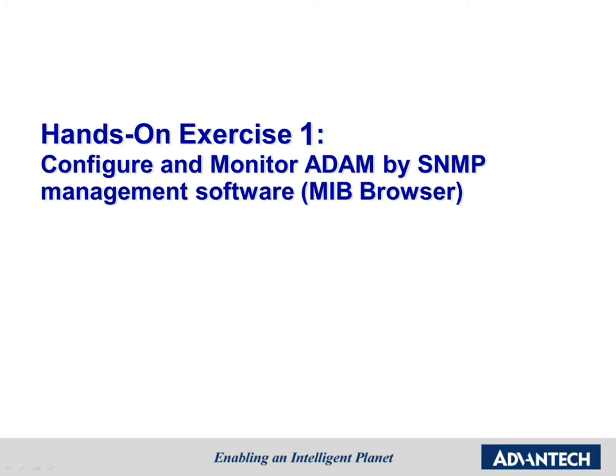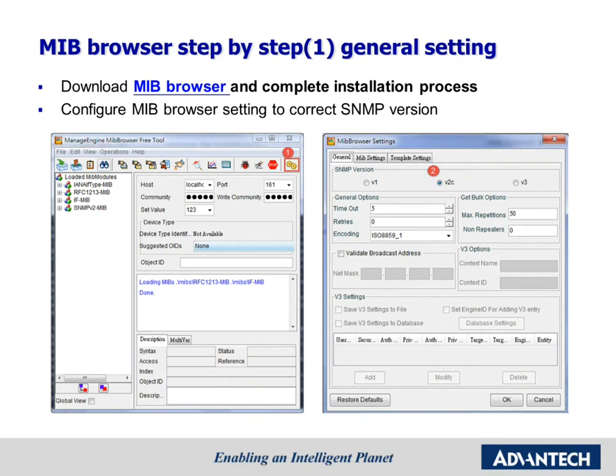Let's go to the first hands-on: configure and monitor ADAM by SNMP management software, MIB Browser. First, please download the MIB Browser. The SNMP protocol has gone through many changes since it was first introduced. v1 has been around for a long time and is still widely supported. v2c is a revision of v2 and is the most popular version of the v2 protocol. The key advantage is the inform and get bulk command, which enhances internet transmission security. v3 is the latest version of SNMP, with primary features of enhanced security providing three services: authentication, privacy, and access control. For the ADAM module, we support v2c and v1, and for our trap messages we support v1.